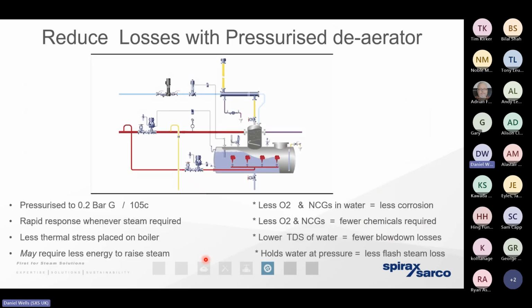Now, an excellent heat sink would be perhaps moving away from that atmospherically vented hot well and instead elevating the pressure and therefore the temperature of the hot water that's held in storage in the boiler house. This is what we call a PDA, or a pressurized deaerator. Because it's under pressure, the water's held at a significantly higher temperature. So we don't need to burn as much gas to raise steam again. And because we're not adding as many chemicals to the water, because it's now at a hotter condition, we're not performing as much blowdown. So we've got a further energy saving. And it also means that we've now got an excellent heat sink to recover any of that vented steam to. We're moving closer and closer towards a zero net loss steam system.